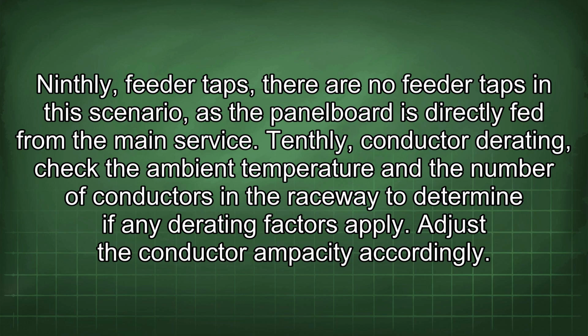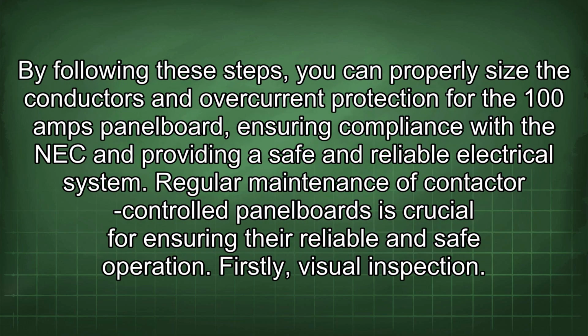Tenthly, conductor derating. Check the ambient temperature and the number of conductors in the raceway to determine if any derating factors apply. Adjust the conductor ampacity accordingly. By following these steps, you can properly size the conductors and overcurrent protection for the 100 amp panel board, ensuring compliance with the NEC and providing a safe and reliable electrical system.